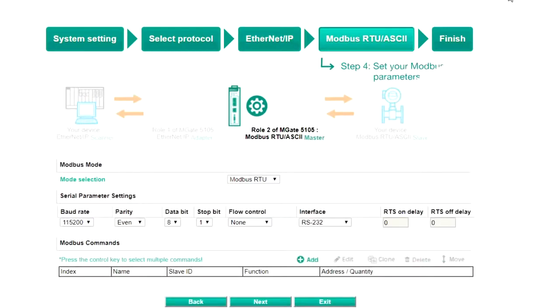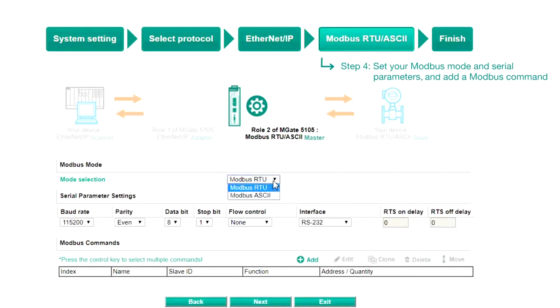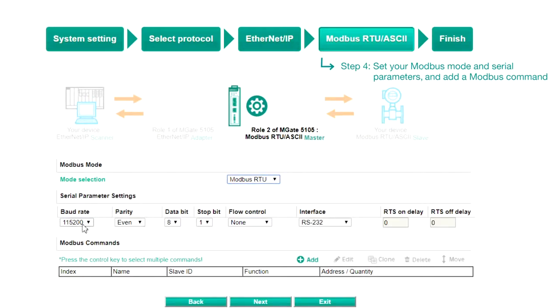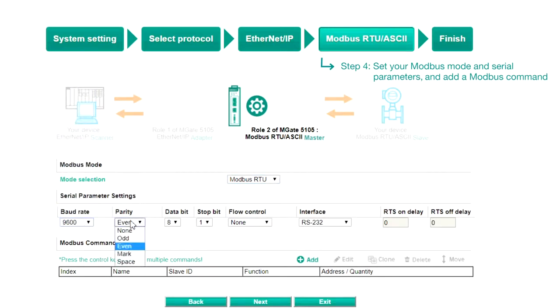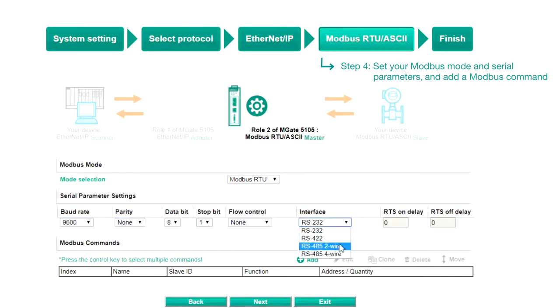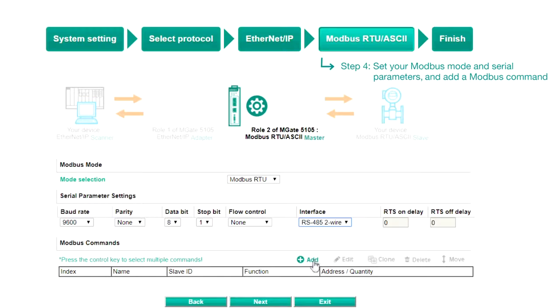Step 4, Modbus RTU ASCII. Select a Modbus mode to use and enter the Serial Parameter settings of your Modbus slave device, such as the Baud Rate, Parity, and which interface to use. To control the speed of the VFD in this demo, we will need to click Add to add a Modbus command.